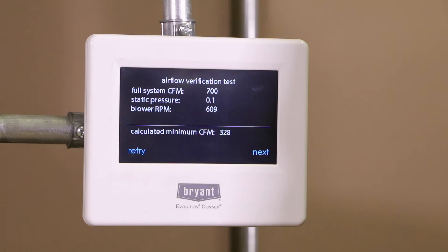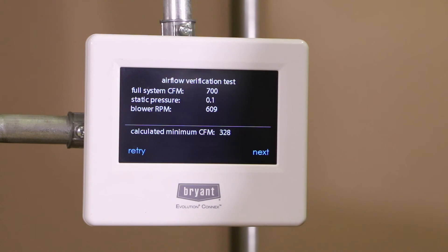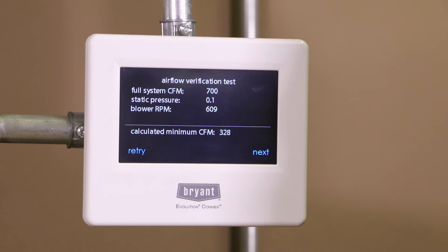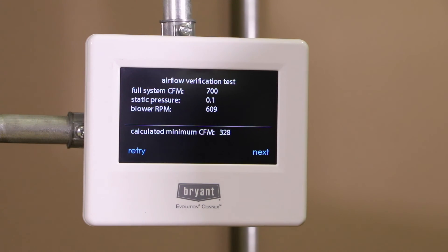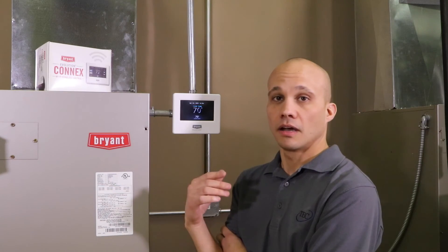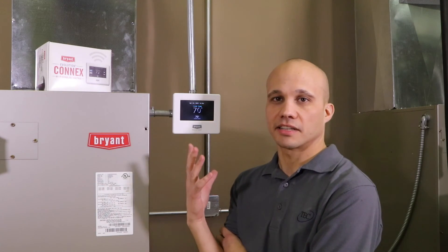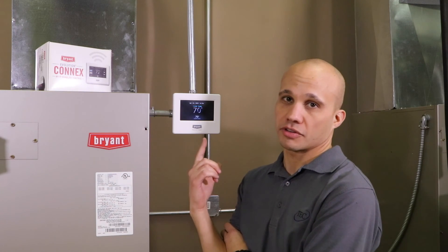Our airflow verification test is complete. We get a small report: our full system CFM is 700, our static pressure is just 0.1 inches — this is obviously a very small system in the lab, so it's much lower than you might normally see — our blower RPM was 609, and our minimum CFM will be 328. You get a nice report on all of that data.